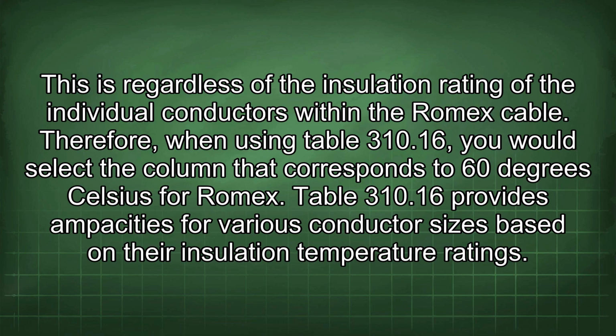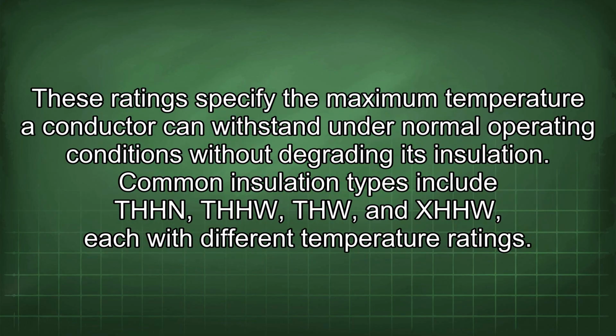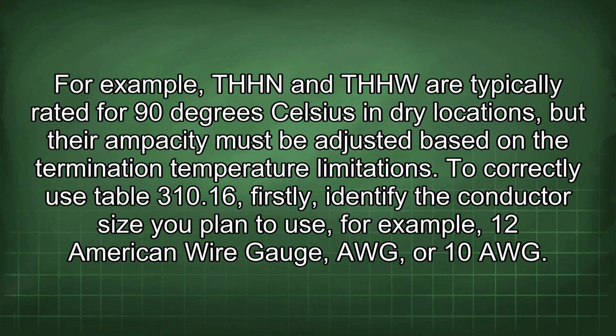Table 310.16 provides ampacities for various conductor sizes based on their insulation temperature ratings. These ratings specify the maximum temperature a conductor can withstand under normal operating conditions without degrading its insulation. Common insulation types include THHN, THHW, THW, and XHHW, each with different temperature ratings. For example, THHN and THHW are typically rated for 90 degrees Celsius in dry locations, but their ampacity must be adjusted based on the termination temperature limitations.